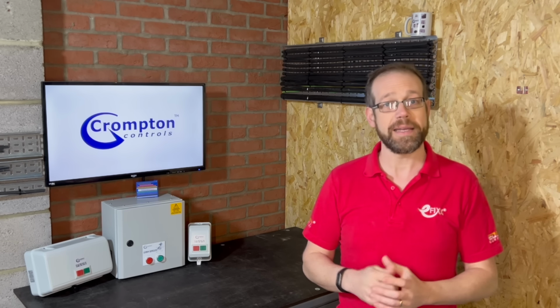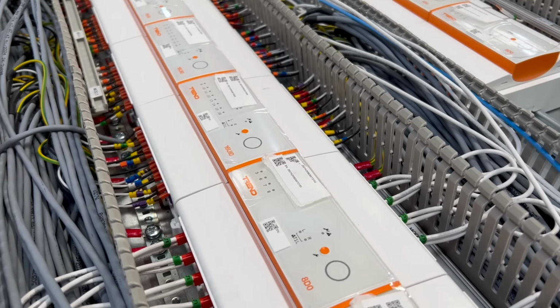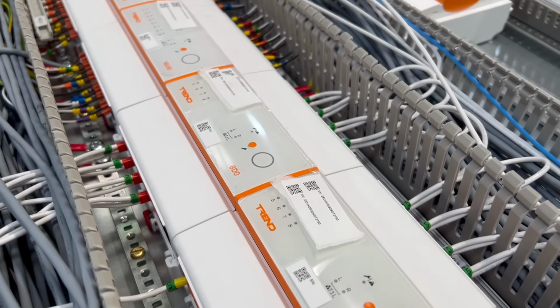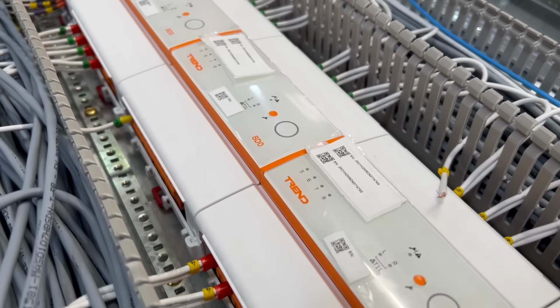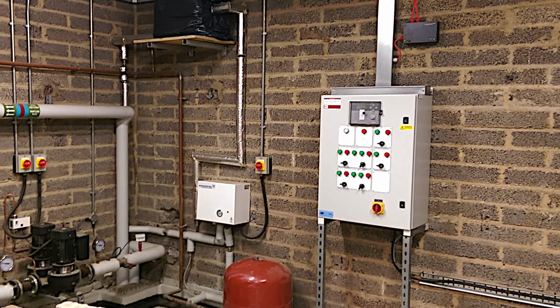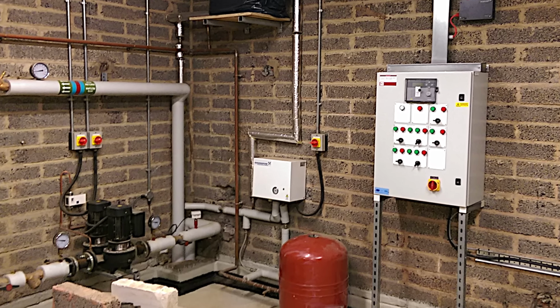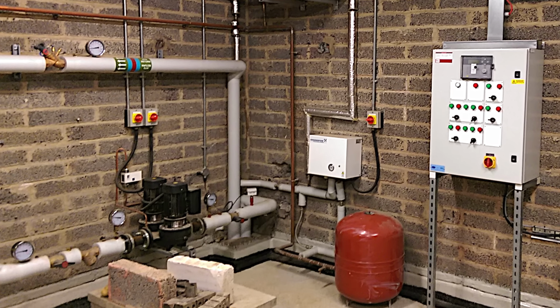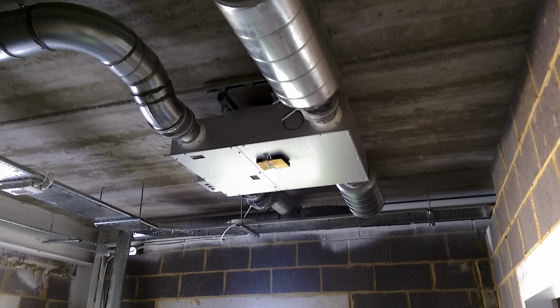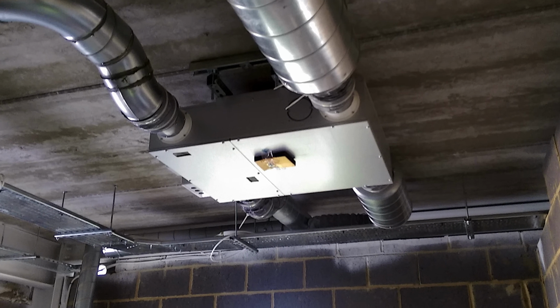Now, here's where BMS systems really show their strength, the networking. Each IQ5 controller isn't just sitting there doing its own little job, they all talk to each other. In a full BMS installation, you might have dozens of these controllers spread around the building, all linked together over a communication network. One controller might detect that the return air temperature is rising, another might be modulating valve positions, and yet another might be adjusting fan speeds, all based on shared data and a central strategy.